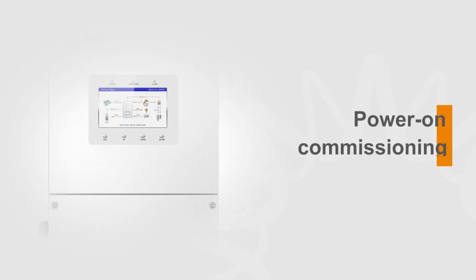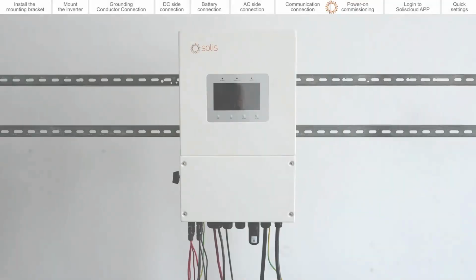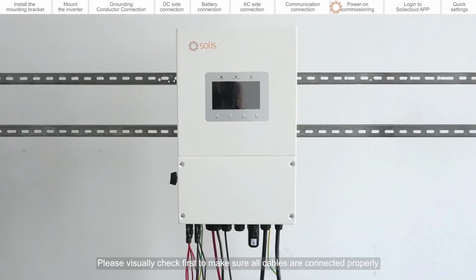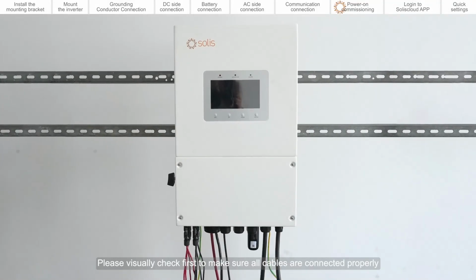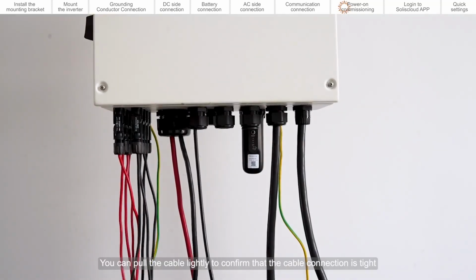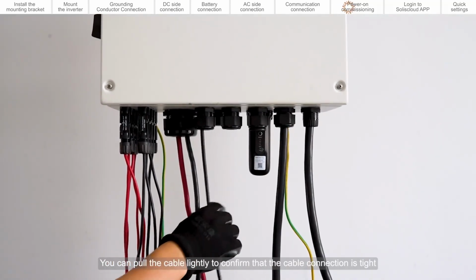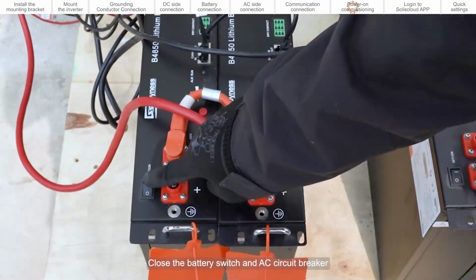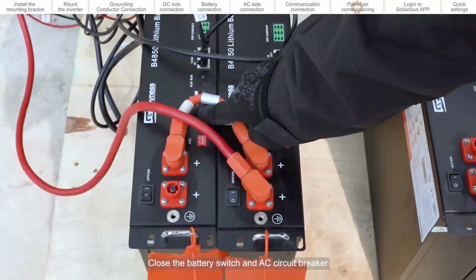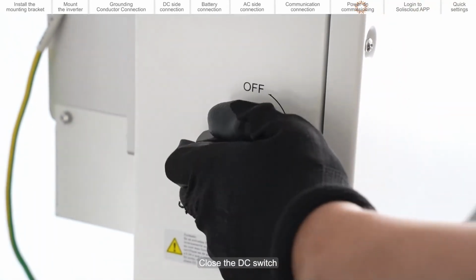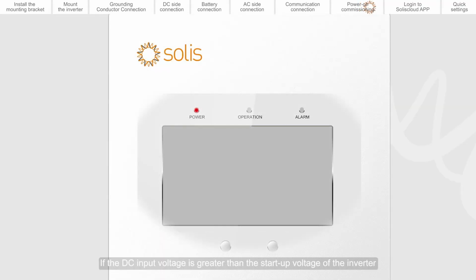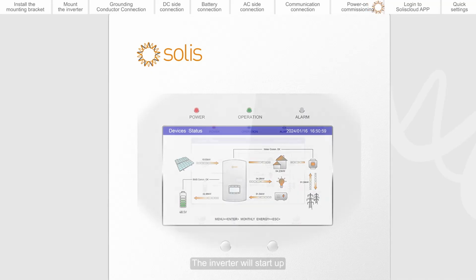Power on commissioning. Please visually check first to make sure all cables are connected properly. You can pull the cable lightly to confirm that the cable connection is tight. Close the battery switch and AC circuit breaker. Close the DC switch. If the DC input voltage is greater than the startup voltage, the inverter will start up.